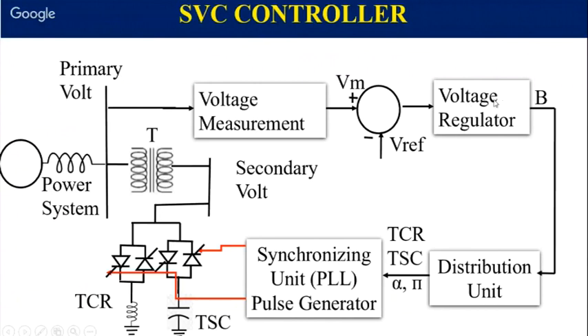The voltage regulator will calculate how much susceptance is required to provide the necessary voltage. Because we have 3 capacitor banks and 1 reactor, it decides which component should be switched on and off to meet this susceptance. Accordingly, it will give pulses to the capacitor and firing angle to the reactor. With the help of PLL blocks, which synchronize with the line, it gives pulses to the switched capacitor and the firing delay to the reactor.